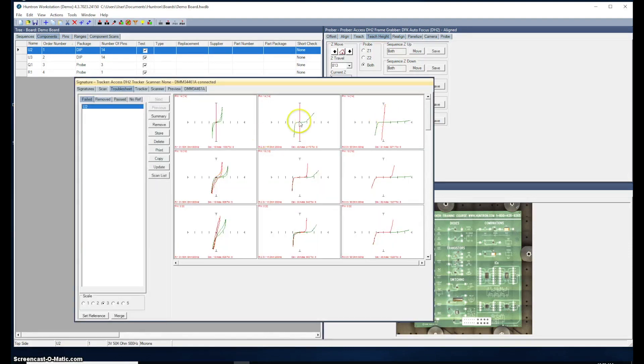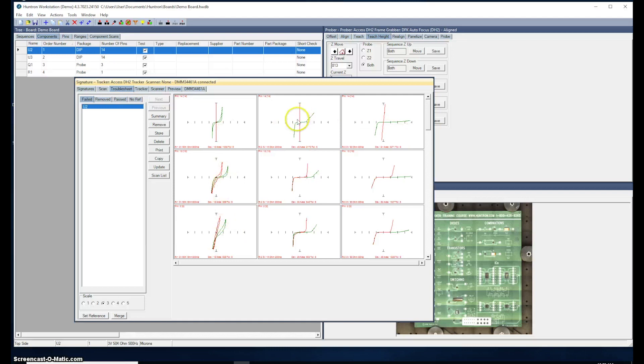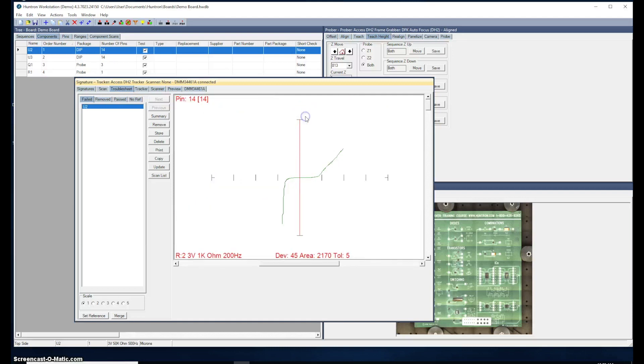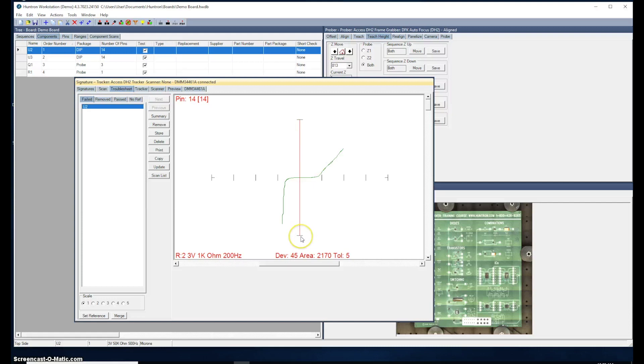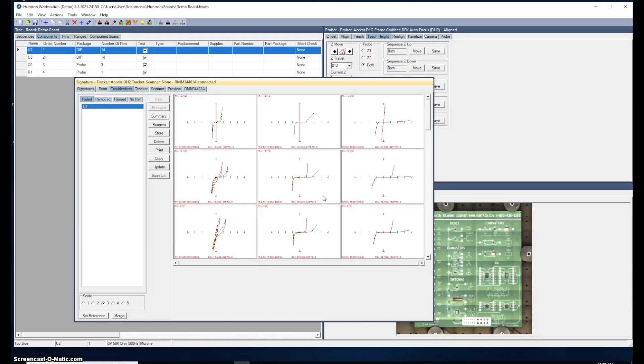What I had done here is I had put a short from the ground to VCC. It's a simple way to create the short here. And it does affect other pins on the device. If you double click on one of the failed signatures, you can see the green signature was from the reference. It's the good board. And then the red signature was from our bad test, the one I had put the fault on. So you can see how the differences are displayed. At this point, you would use this information to help you troubleshoot the circuit board. Obviously, we'd be looking to see if we could find the short problem on the circuit board.